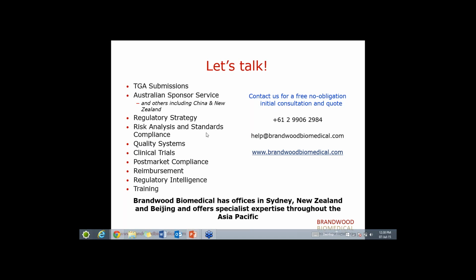The other question I've got is, it's quite a good question. For a manufacturer, if they already have a TGA Conformity Assessment certificate and also an EC certificate, what should they do following the change? That's a good question. From the last slide, when I mentioned that the new law allowed local Australian manufacturers to use an EC certificate, the answer is you don't need both. You only need one now.